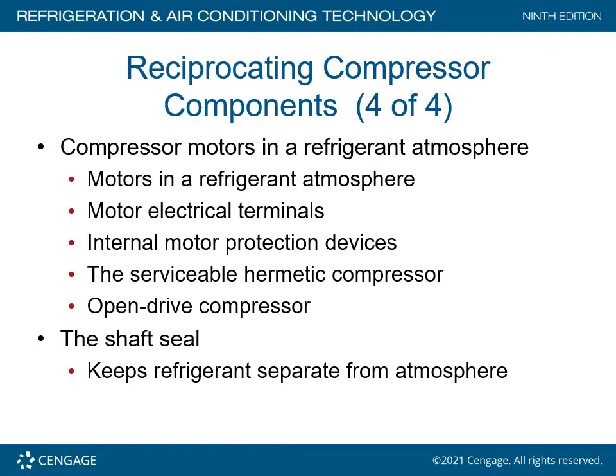For the serviceable hermetic and open drive compressors, a shaft seal is required when there is an external drive mechanism. It keeps the refrigerant separate from the atmosphere. Shaft seals do fail — they are designed to wear out over a long period of time depending on how long the compressor operates.